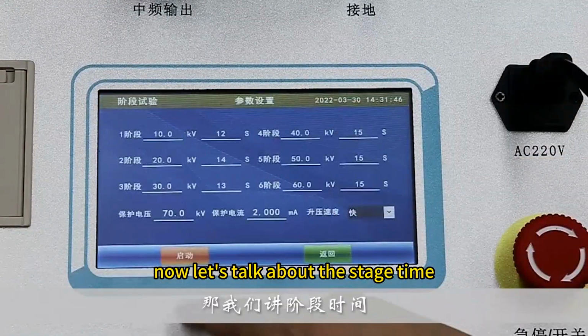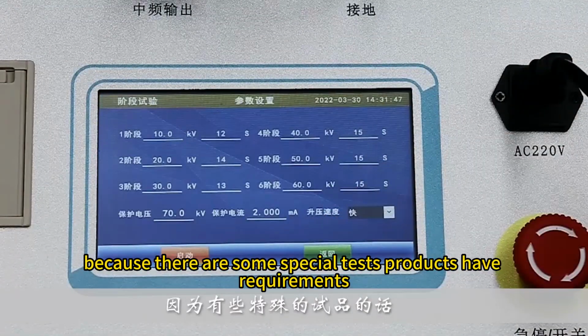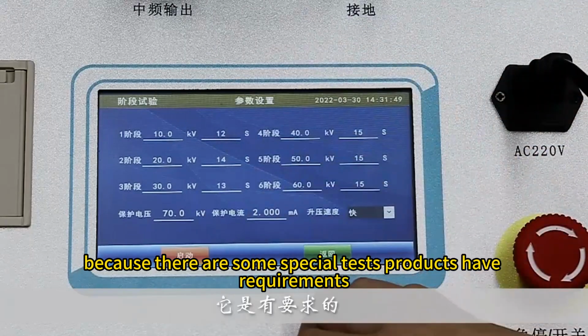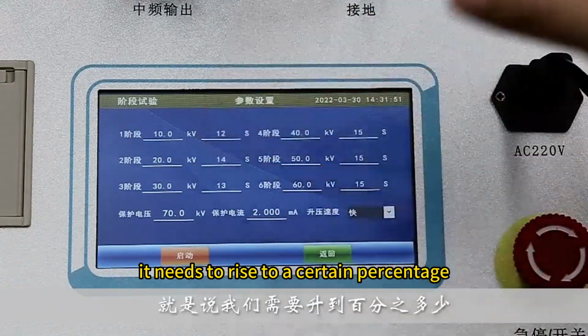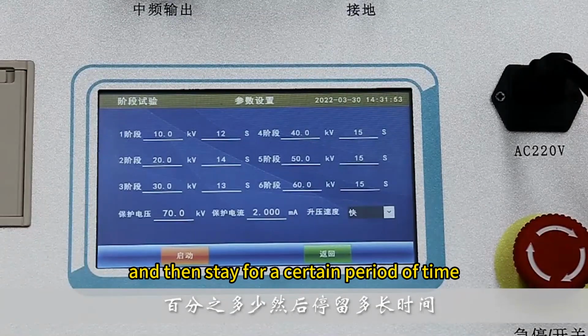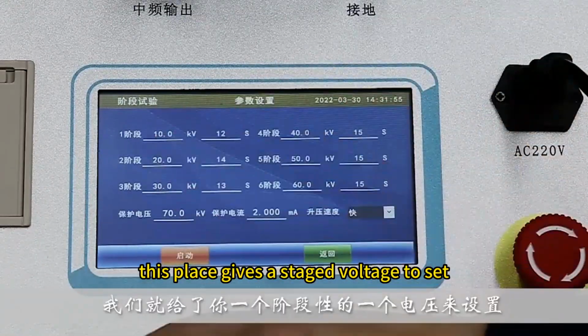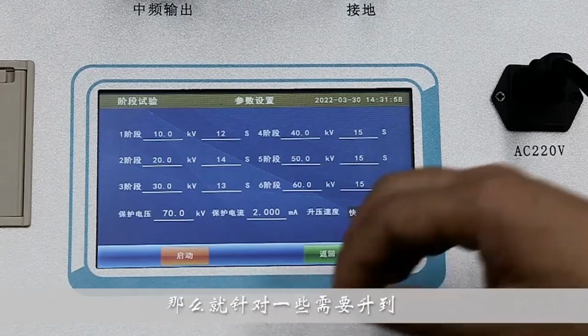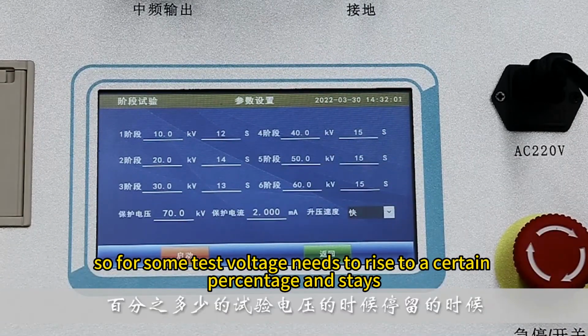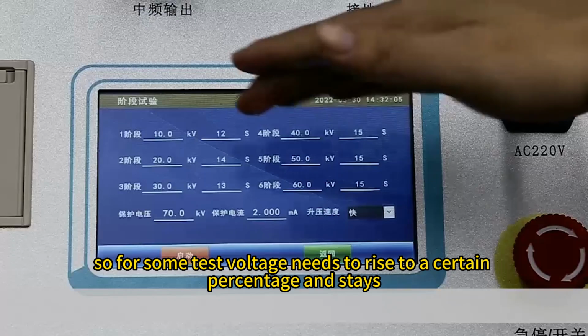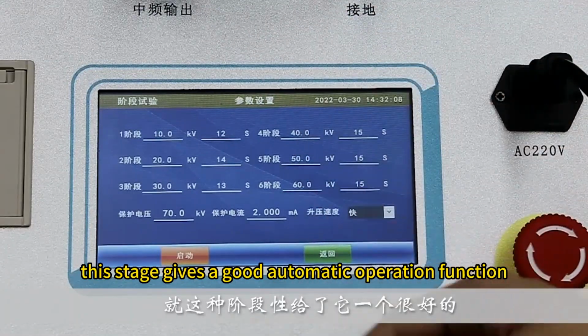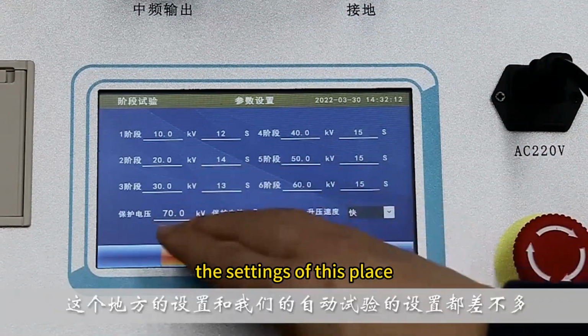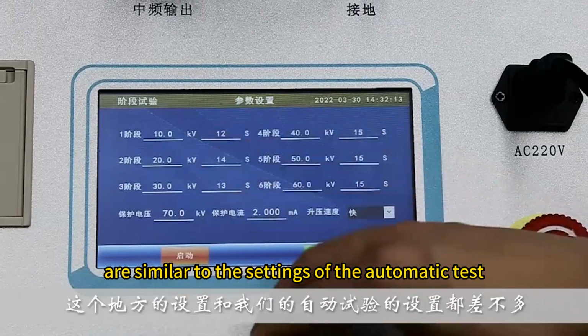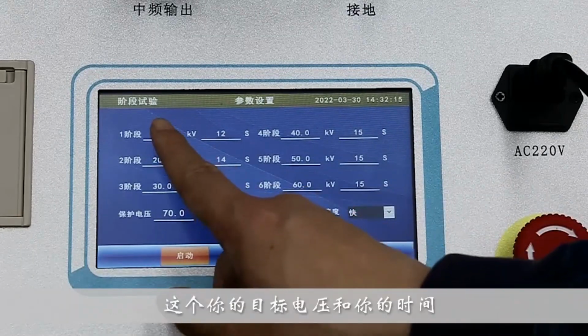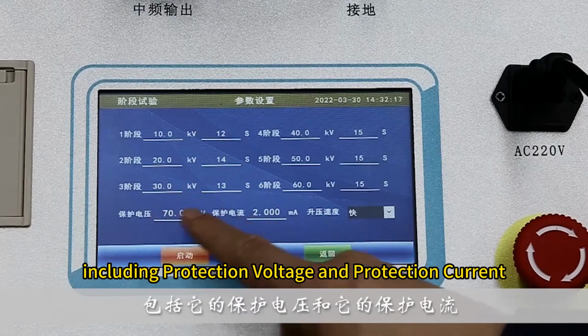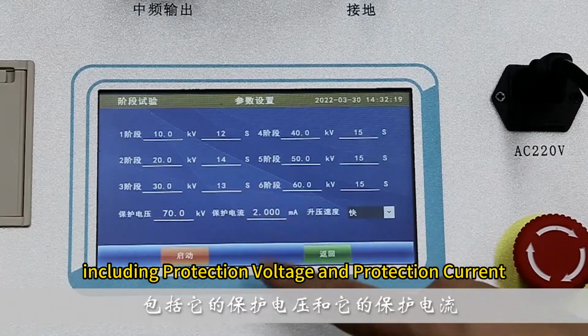Now let's talk about the stage time, because some special tests have requirements. The voltage needs to rise to a certain percentage, and then stay for a certain period of time. This place gives a staged voltage to set. So for some tests, the voltage needs to rise to a certain percentage and stay. This stage gives a good automatic operation function. The settings of this place are similar to the settings of the automatic test: the target voltage and time, including protection voltage and protection current.